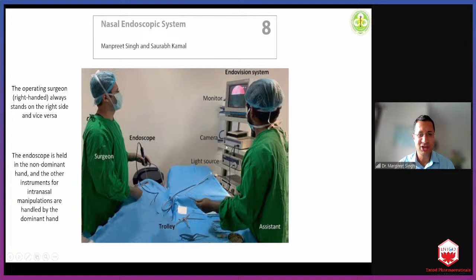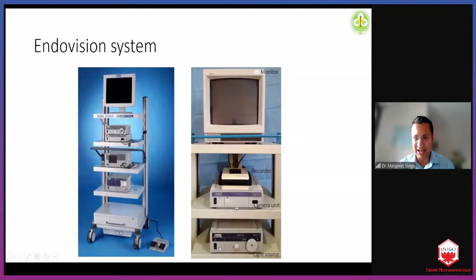The endoscope is held in the non-dominant hand, and in the dominant hand we use the instruments to operate and do the manipulations. This is how the endovision system looks. Karl Storz is one of the companies, no financial interests; there are many others, like Olympus and Stryker. This is the first system we had in PGI, in picture number 2 on the right side: the monitor, the camera unit, and the light source. I still use this light source, but the camera unit and the monitor have been changed.